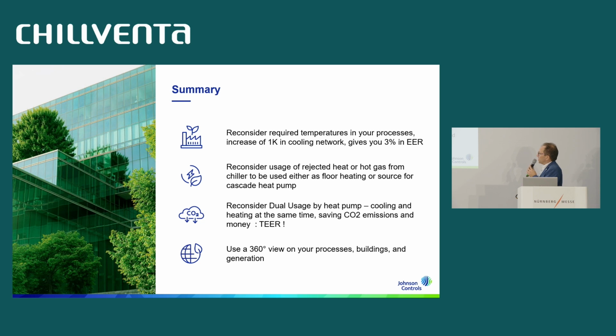So to sum up, I urge you to reconsider temperatures. You can easily spare money. You can easily enhance your efficiency by increasing the required temperatures, or have a deep look at the required temperatures. Furthermore, reconsider usage of the rejected heat. Use it directly, or if not possible, use it as a source for a heat pump. And if you do a new installation, please think about a two-stage heat pump to have cooling and heating at the same time, saving CO2 emissions and money. And of course, use a 360 view on all of your buildings, processes, and temperatures needed. And still there's more to come.